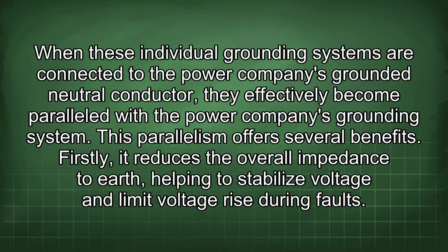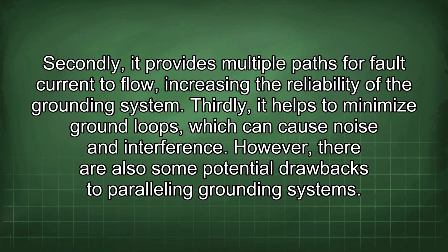Firstly, it reduces the overall impedance to Earth, helping to stabilize voltage and limit voltage rise during faults. Secondly, it provides multiple paths for fault current to flow, increasing the reliability of the grounding system. Thirdly, it helps to minimize ground loops, which can cause noise and interference.